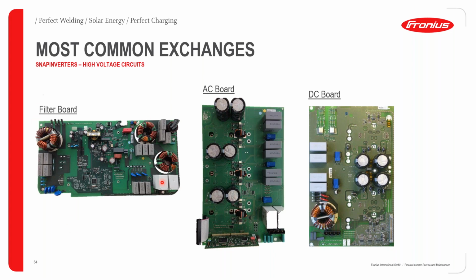Starting off with the filter board. The filter board is the first point of contact between any high voltage or low voltage AC or DC components of the inverter. If you look at the bottom left of this filter board, this is where your DC will enter the inverter, getting filtered via a combination of inductors and capacitors to ensure you now have a nice clean DC voltage, which will then go to the DC board.